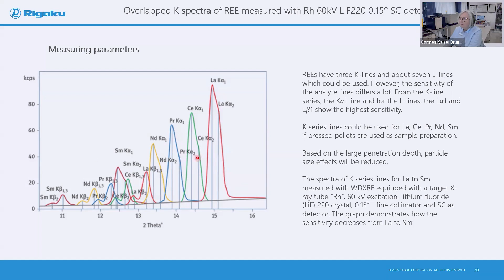So typically, for the elements lanthanum, cerium, praseodymium, neodymium, and samarium in the pressed powder, we can use the K series of lines, but this is based on a large penetration depth, and the particle size effects will be reduced. The spectra of these K lines for these elements can be measured with the crystal that I mentioned. And here's an example of the spectra. You can see there's a lot of overlap, and of course, it's important for us to separate this.